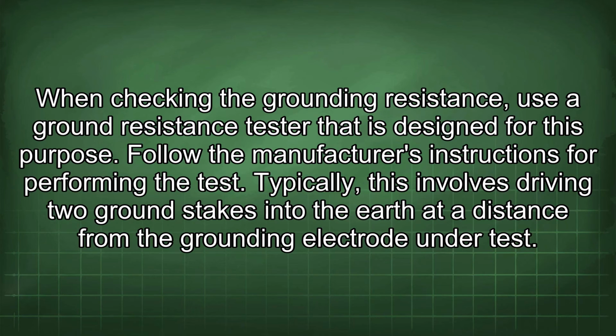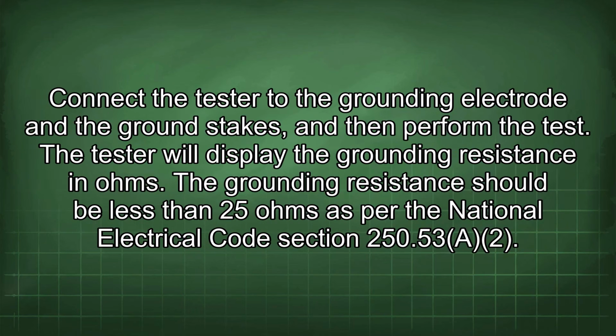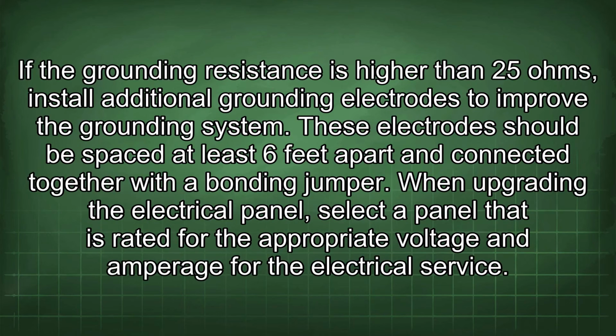Typically, this involves driving 2 ground stakes into the earth at a distance from the grounding electrode under test. Connect the tester to the grounding electrode and the ground stakes and then perform the test. The tester will display the grounding resistance in ohms. The grounding resistance should be less than 25 ohms as per the National Electrical Code section 250.53(A)(2). If the grounding resistance is higher than 25 ohms, install additional grounding electrodes to improve the grounding system.